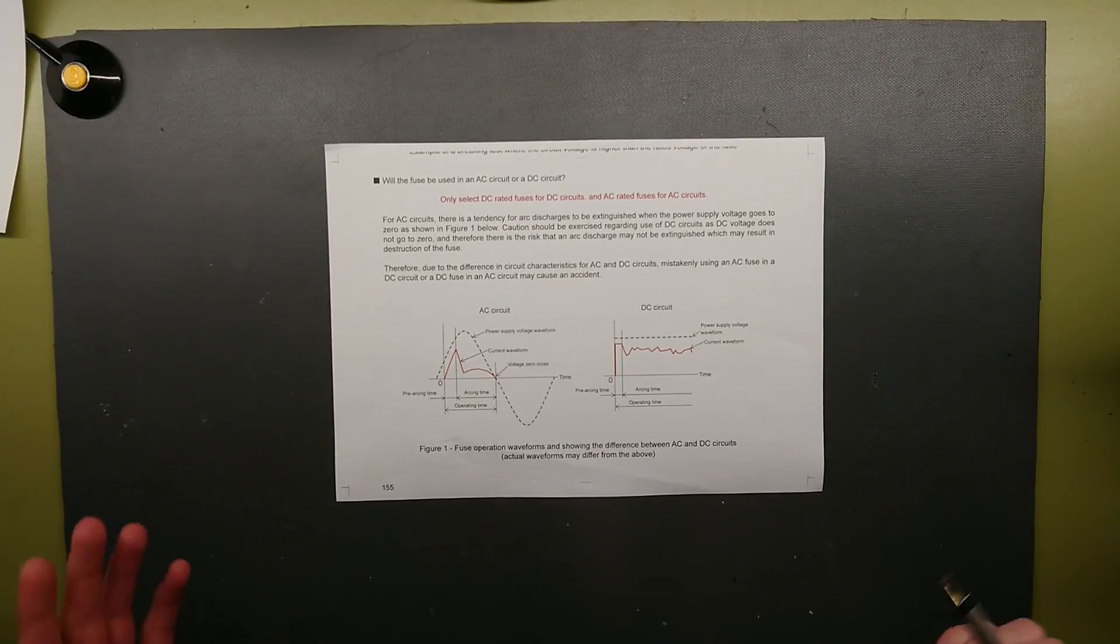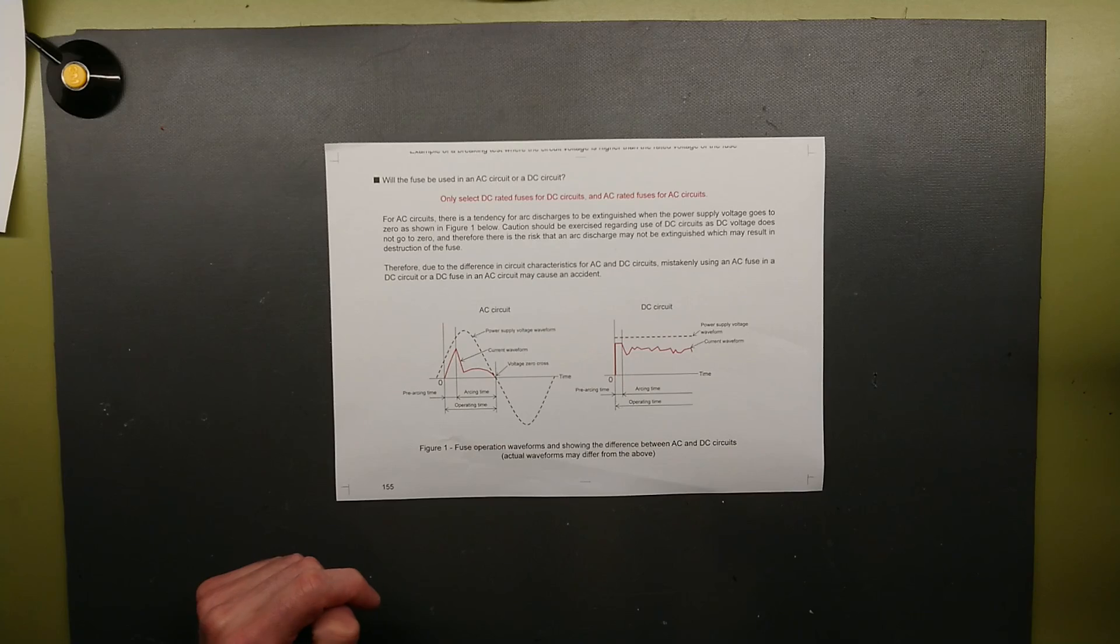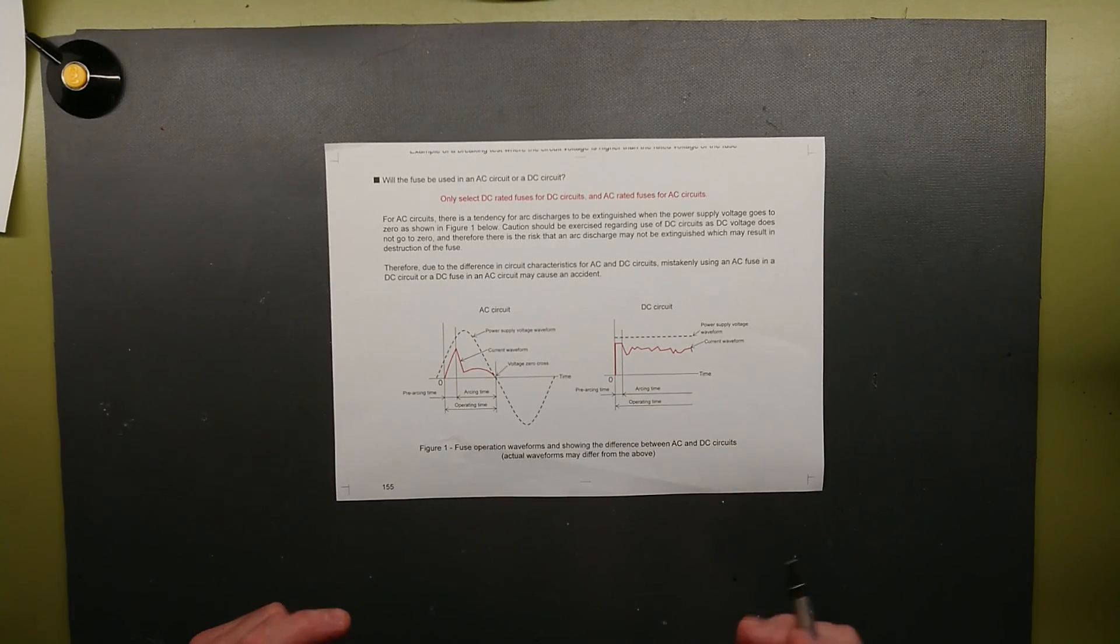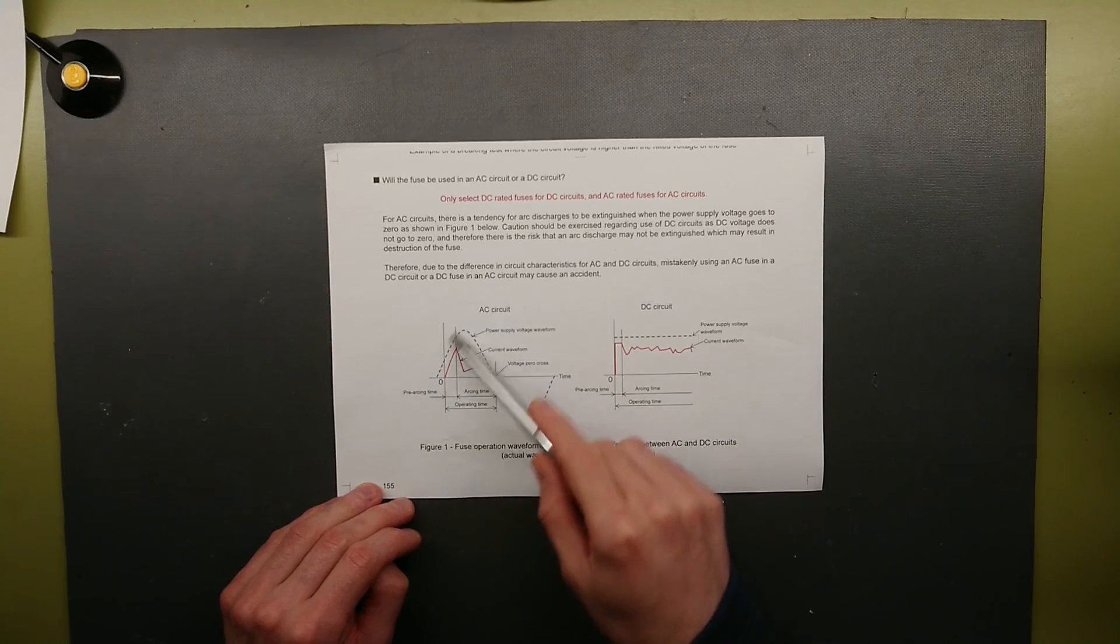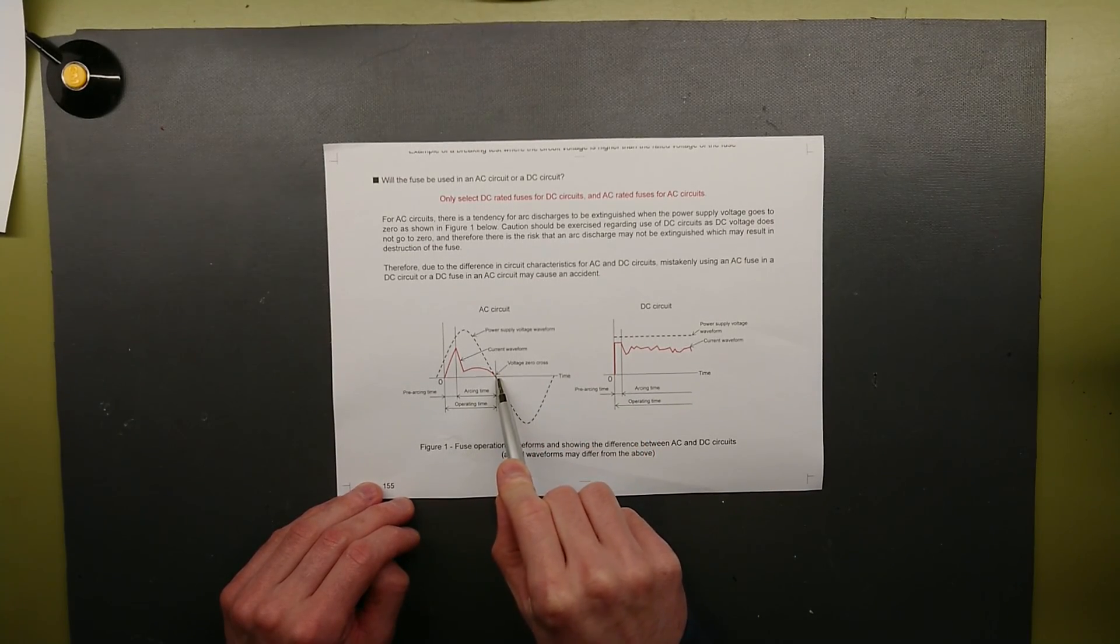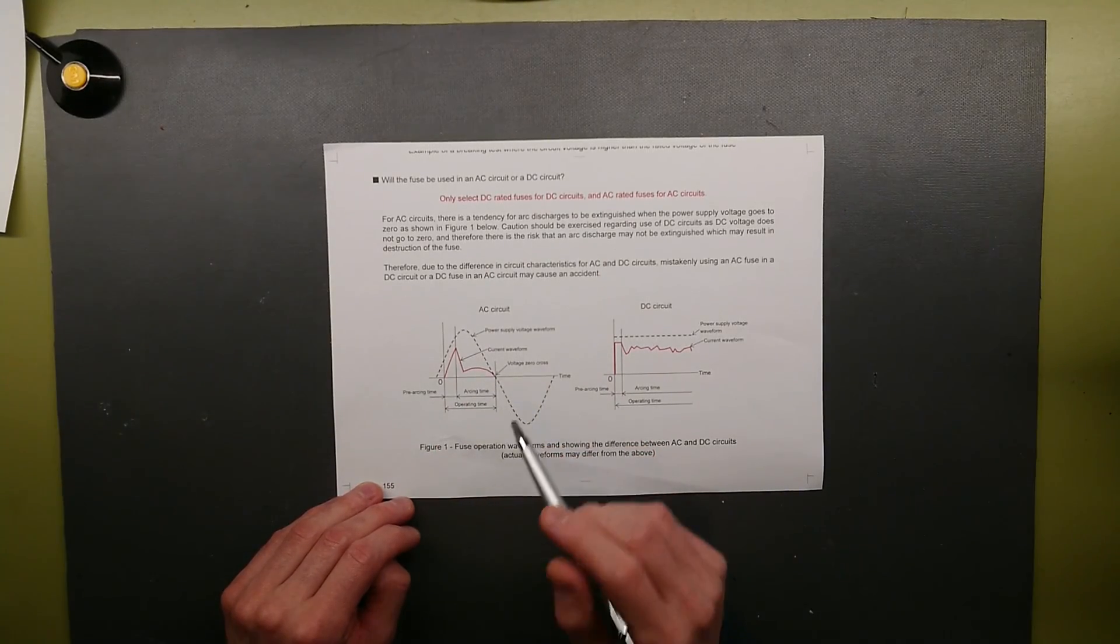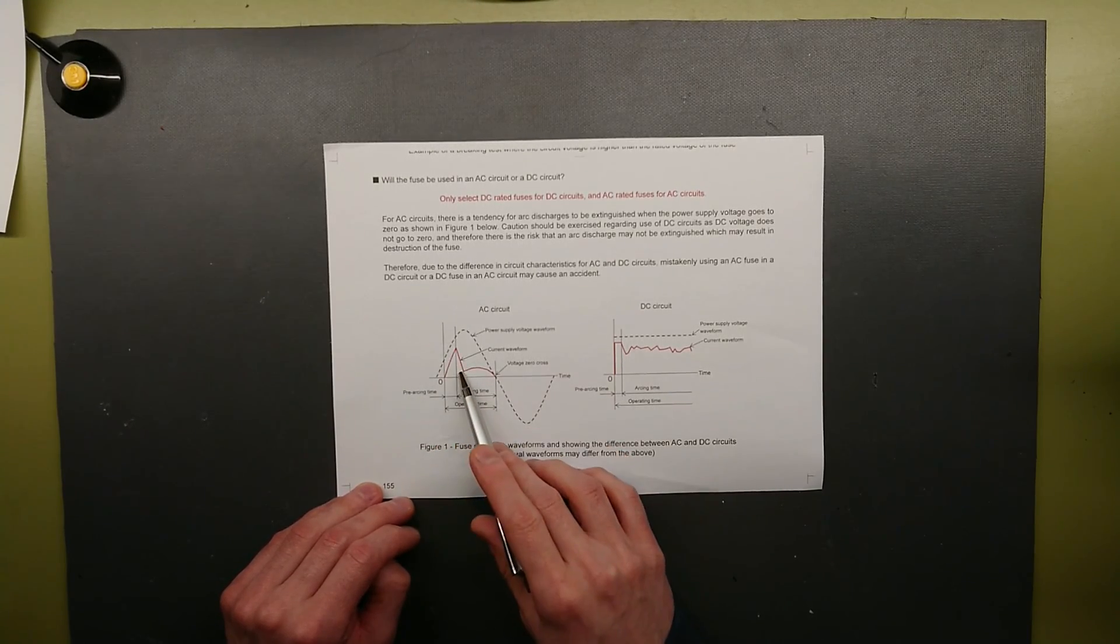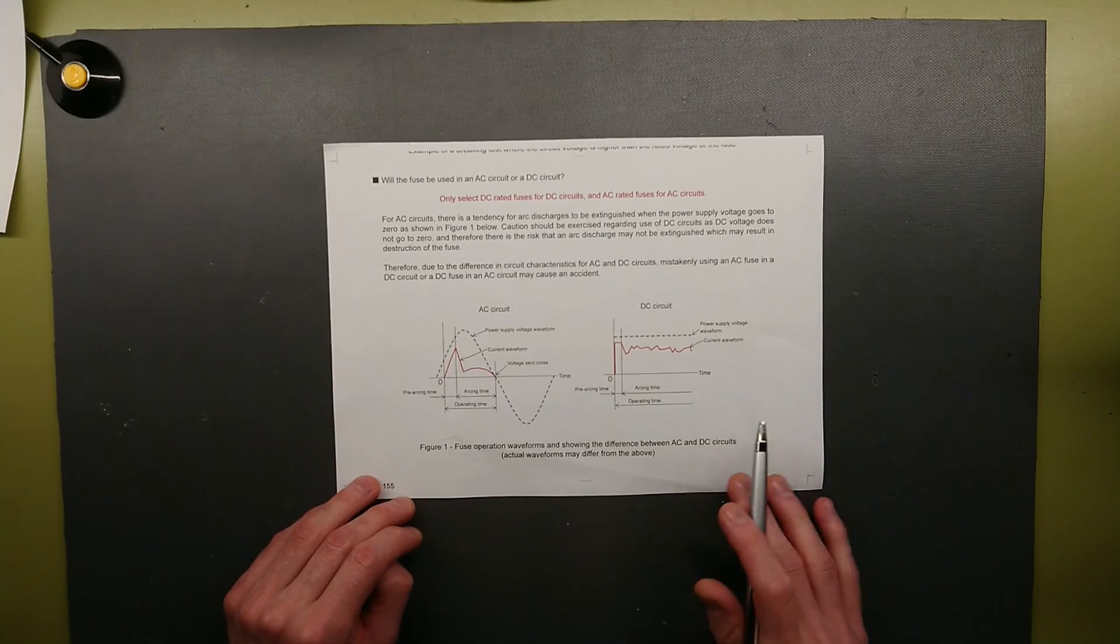The differences between DC and AC fuses has to be seen in the light of the current and voltage that they conduct and the kind of circuits that they protect. In an AC circuit the AC voltage is alternating between positive and negative. There will at any given time be a place where the AC voltage will cross down to zero, and that will most likely extinguish the arc as there is nothing to drive the current anymore.